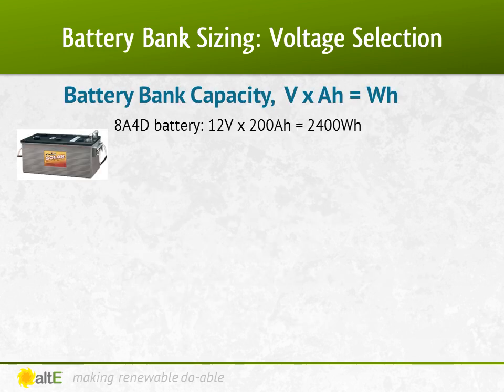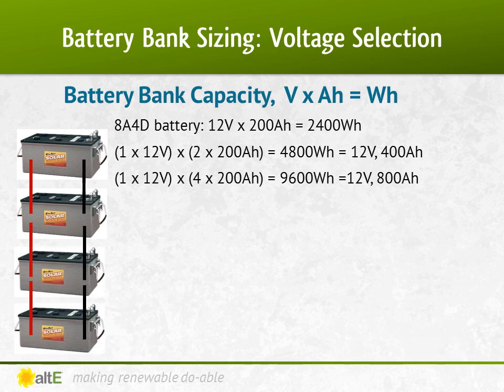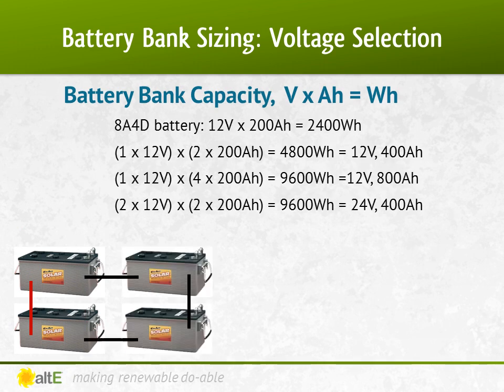Let's get into this a little bit deeper. We'll use an 8A4D battery as an example — it is 12 volts and 200 amp hours. 12 volts times 200 amp hours equals 2400 watt hours for one battery. Remember that wiring in parallel, with the pluses together and the minuses together, increases the amp hours but keeps the voltage the same. And wiring in series, plus to minus, increases the voltage but keeps the amp hours the same. If I needed 4800 watt hour capacity, I can wire two of these batteries in parallel. However, if I needed 9600 watt hours, I would need four of these batteries. Since I want to limit the number of parallel strings I use, I can't wire them all in parallel, but I could wire them in two parallel strings of two in series. In doing so, I made a 24 volt, 400 amp hour battery bank. 24 volts times 400 amp hours equals 9600 watt hours.